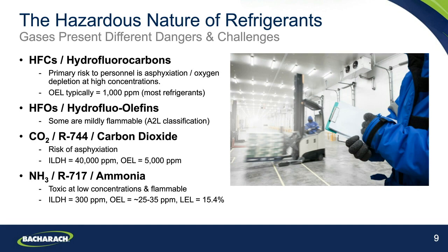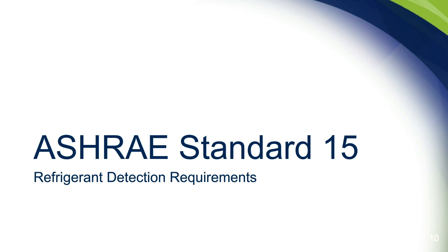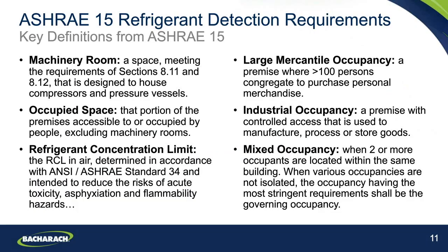So broadly speaking, these are the reasons we are looking for refrigerant leaks. It is because of the range of hazards that can present themselves if there is a leak from the refrigeration system. So let's look at ASHRAE Standard 15 and look at the refrigerant detection requirements within there. I've highlighted here some of the key definitions from within the standard. These are just to give relevance to particularly where we tend to see leak detection being employed. So a machinery room, of course, we should all be familiar with, is the space that is designed to house the compressors and pressure vessels that drive a centralized refrigeration system.